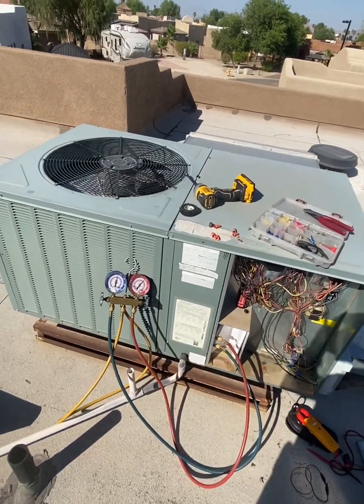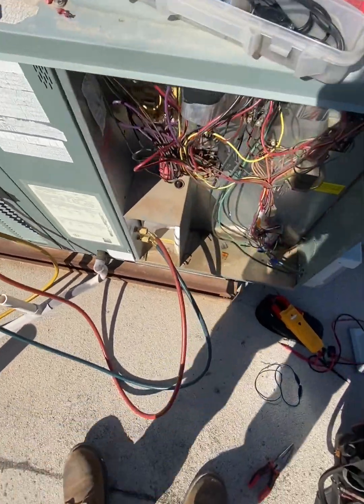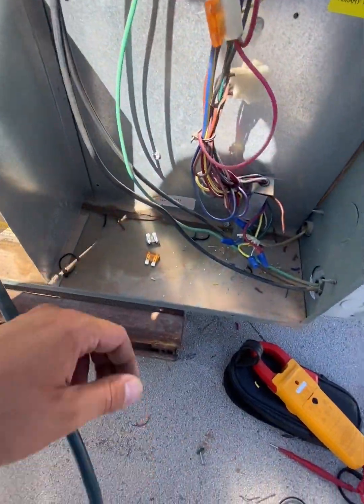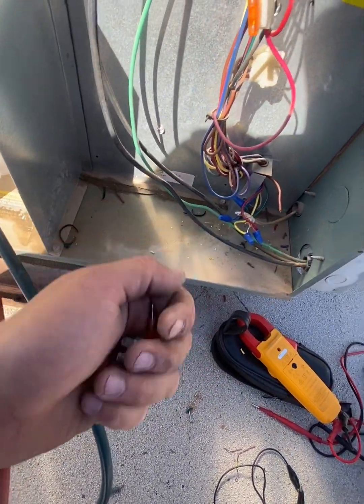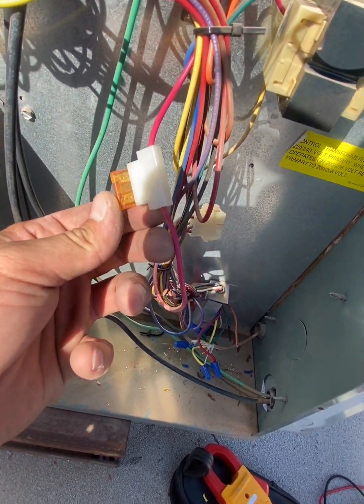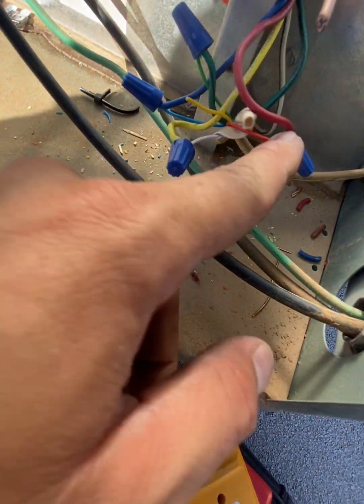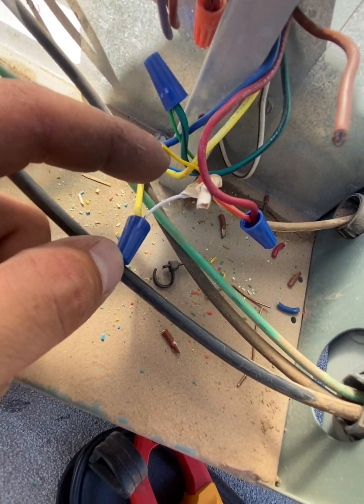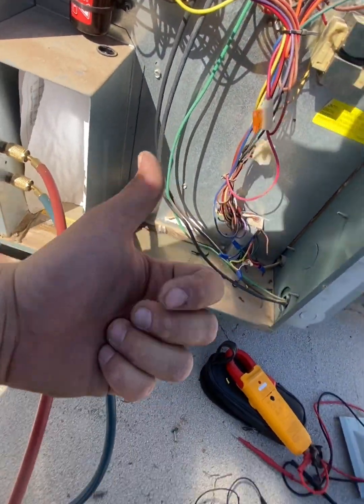One piece of advice that I'm going to give you guys is to always listen to your customer. This lady told me that when she turned on the cooling mode, the unit never worked again. So then right from the beginning, I knew it was going to be a problem with the Y1. If you need any extra help with the low voltage short and you have a question, go ahead and hop on the comment section and I'll be glad to help you. Until next one guys, thank you for watching.